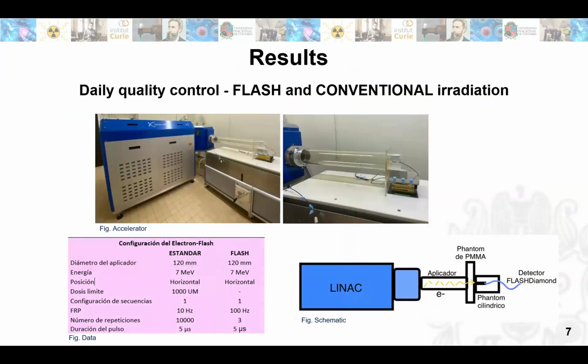Next, a daily QA protocol was developed to ensure the stability of the monitoring system of the Electron Flash linac in both conventional and flash irradiation modes. A cylindrical applicator of 120 millimeters was attached to the accelerator jaws. At the end of the applicator, an additional 10 millimeter PMMA, polymethyl methacrylate, plate was placed to ensure adequate build-up before reaching the detectors.